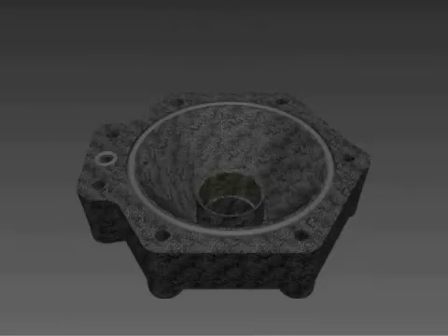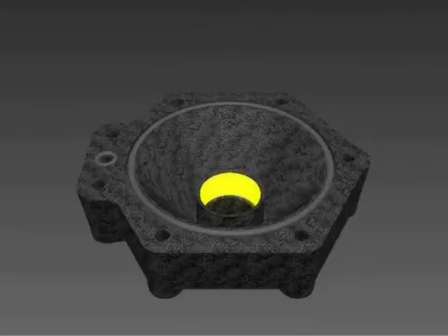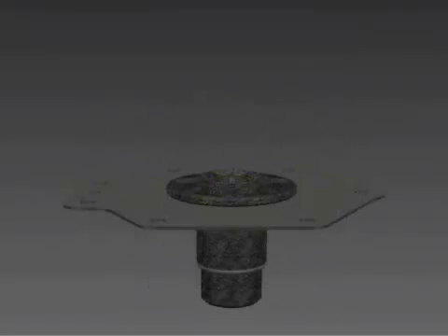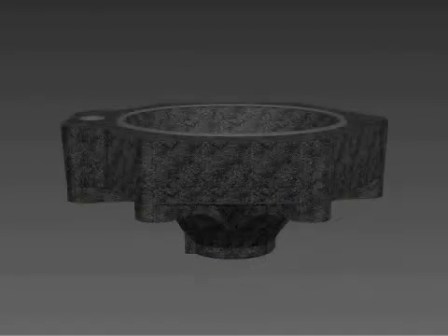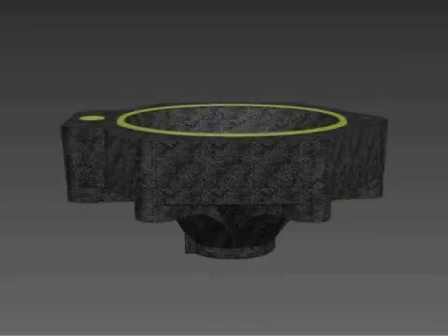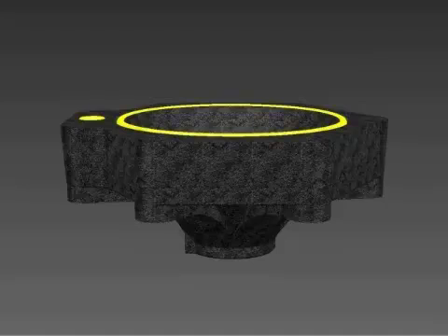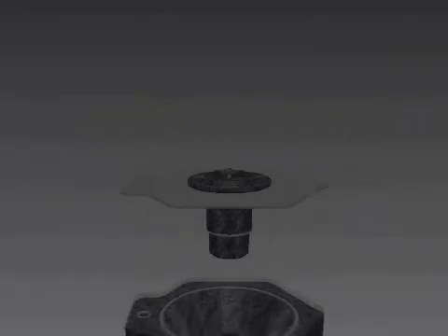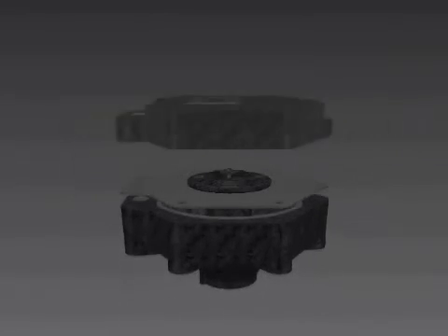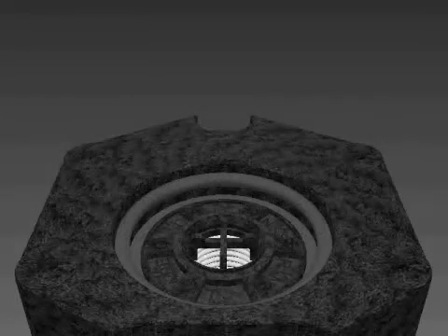Clean and inspect the bore in the cover. Lubricate the O-ring on the plunger. Place the large and small O-ring into the grooves in the cover. No lubrication is required. Place the cartridge assembly into the cover. You will center the flange on the diaphragm and line up the bolt holes with the cover.